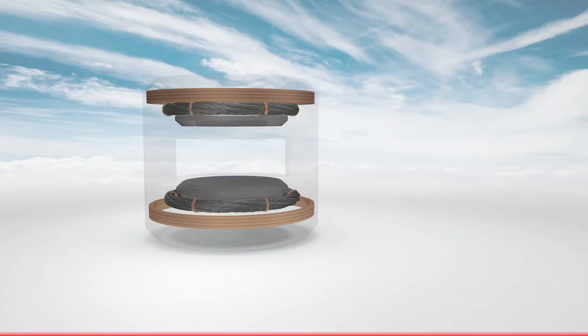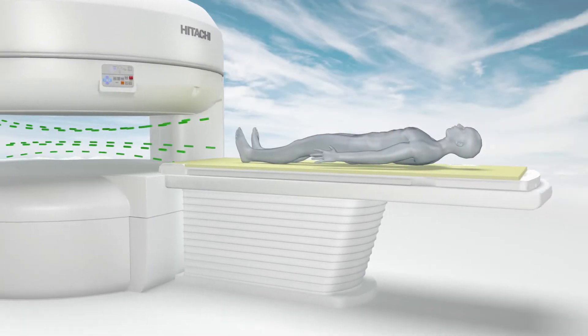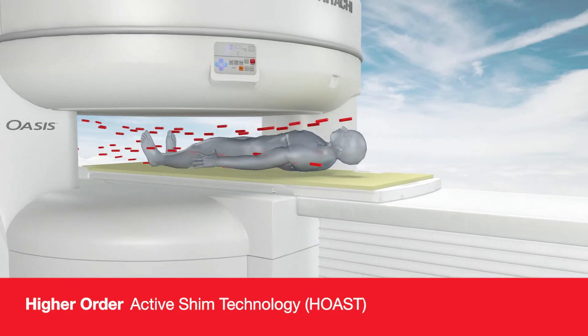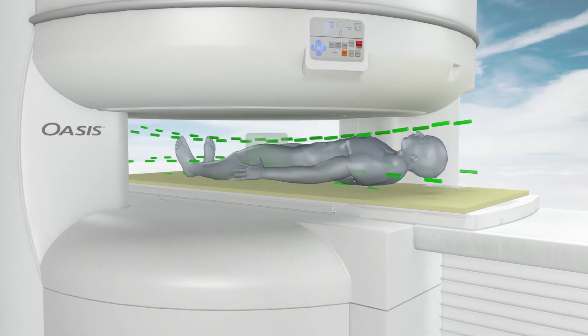It delivers excellent image quality, acquisition times, and workflow on par with 1.5T systems. A key capability with OASIS is the embedded higher order active shim technology, or HOAST, which delivers the highest uniformity and consistent fat saturation for every exam and every anatomy scanned.